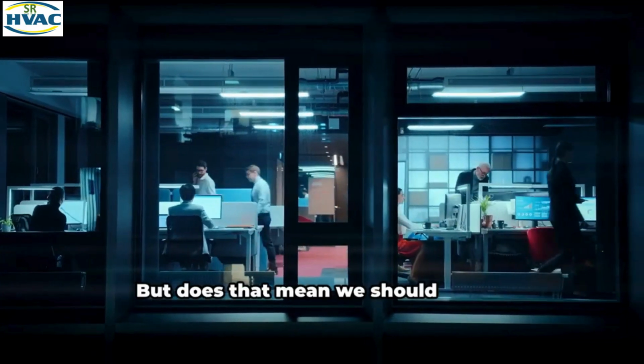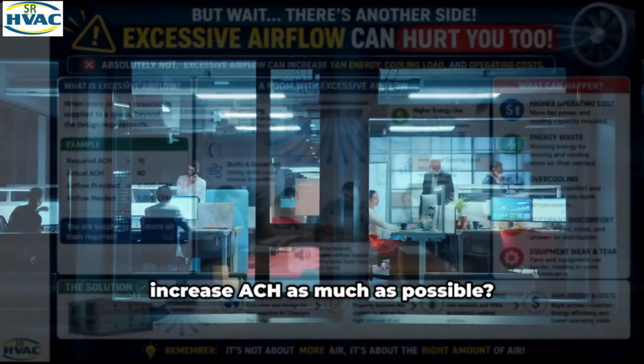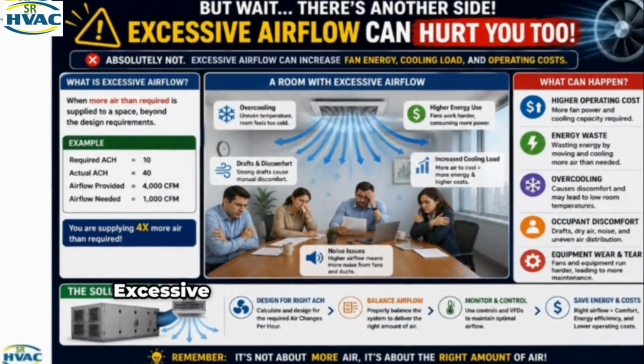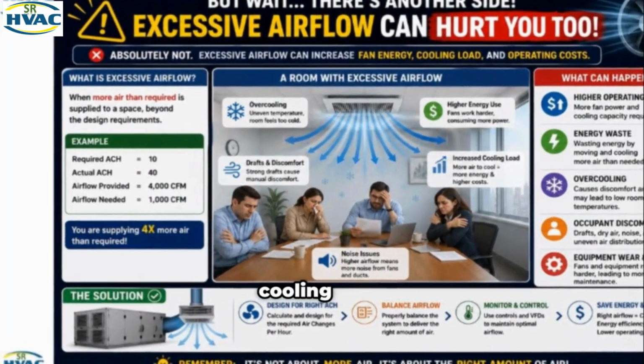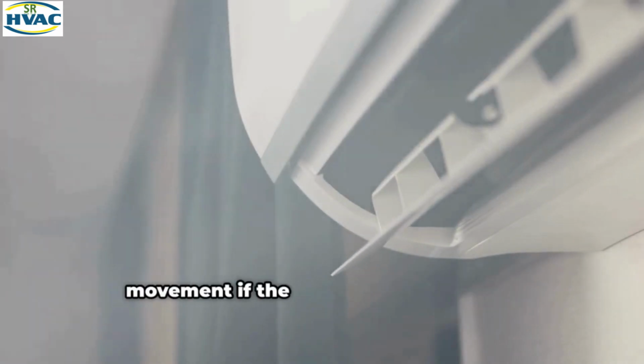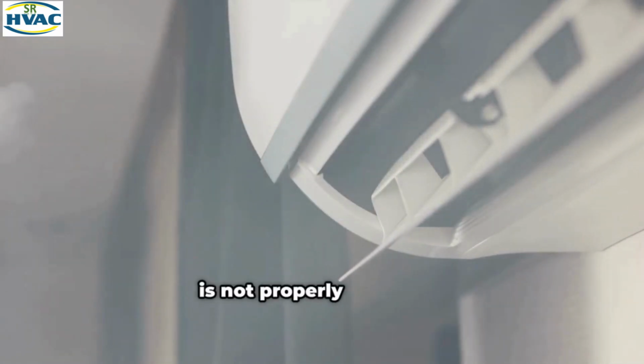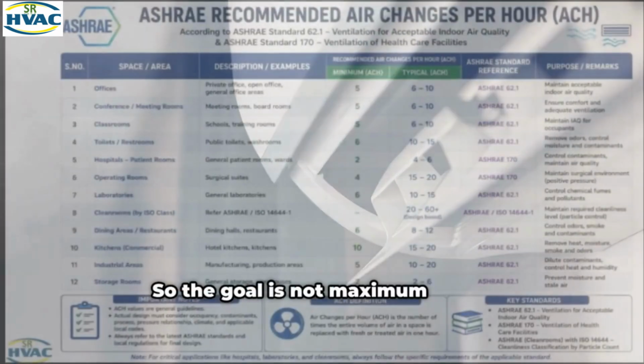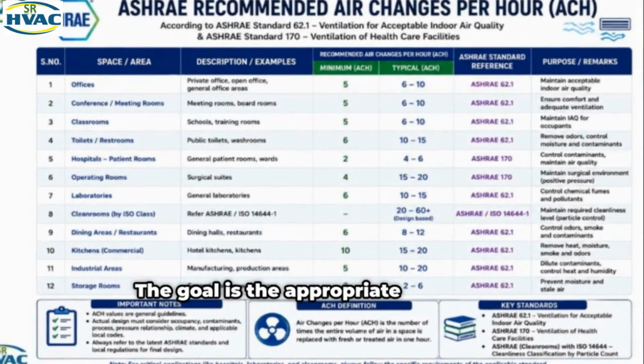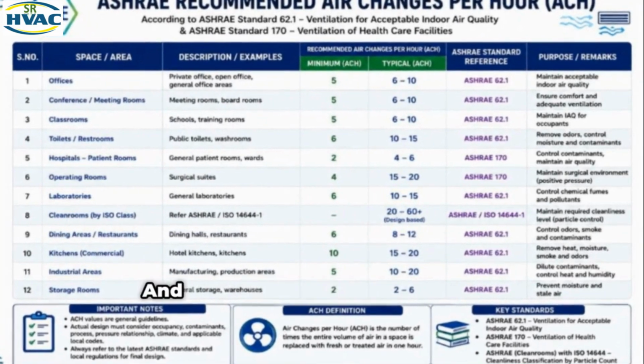But does that mean we should simply increase ACH as much as possible? Absolutely not. Excessive airflow can increase fan energy, cooling load, and operating costs. It can also create uncomfortable air movement if the air distribution system is not properly designed. So the goal is not maximum ACH. The goal is the appropriate airflow for the application. And this is where HVAC engineering becomes interesting.